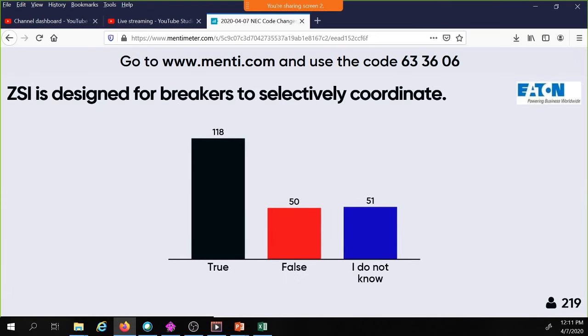ZSI is designed for breakers to selectively coordinate. I love this. One of these days, this question is going to be answered correctly, and I'm going to be jumping around the room. The 123, 124 of you, unfortunately, you're in the wrong bucket. You should be down there in that 56 and 57 bucket. Those guys were probably in the class last week, because I went over this. And if there's anybody in that 125 bucket that was in my class last week, send me back those PDH hours, because I taught this last week when we talked about selective coordination.